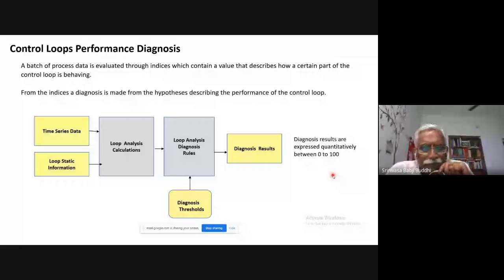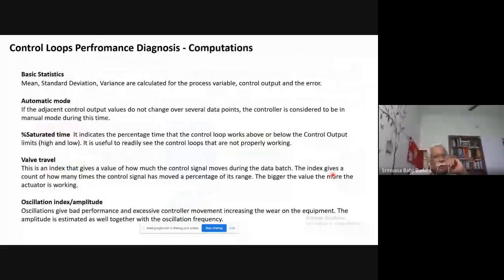So now I will tell you about the various computations that are carried out for the performance monitoring of these control loops. First, we do the basic statistics calculation. That means mean value, averaging the value, standard deviation, and variance are calculated for all the process variables, control output, and the error signals. Then we have another calculation that is related to automatic status.